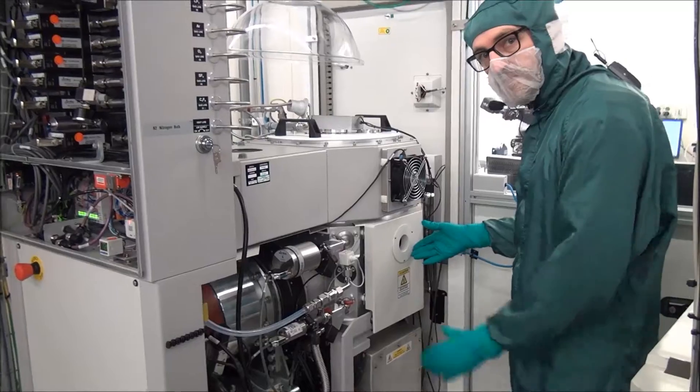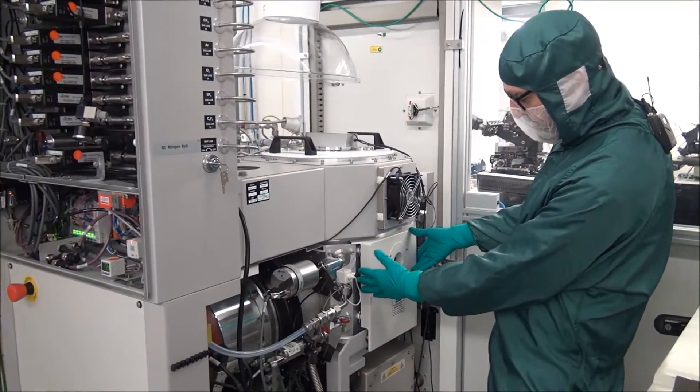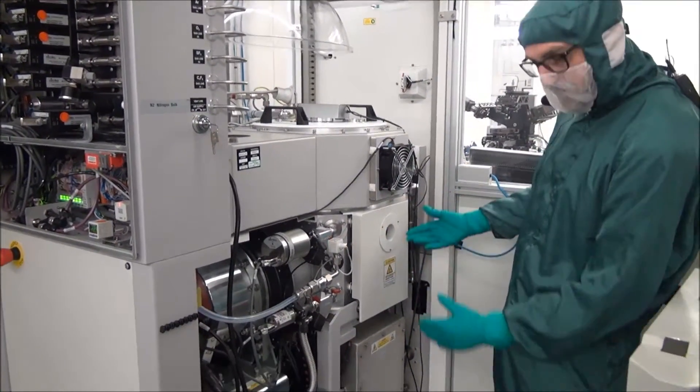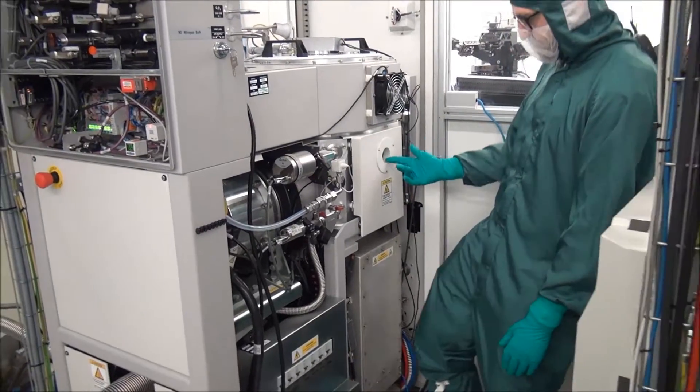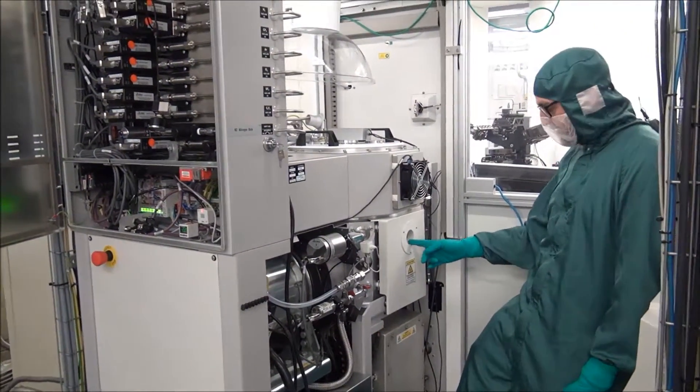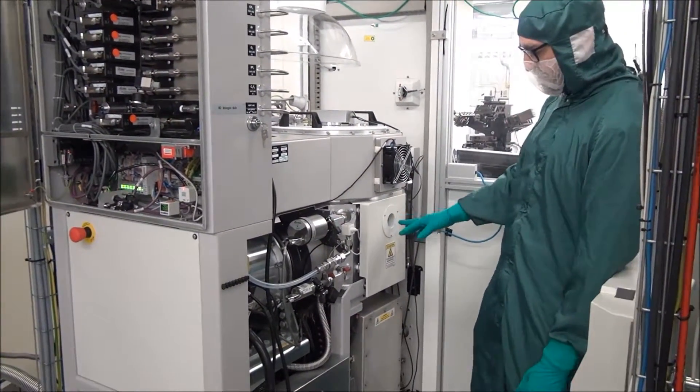The wafer itself is sitting in the bottom part of the chamber. And when the plasma is running you can actually see the plasma if you look through the window here. You will be able to see some light.